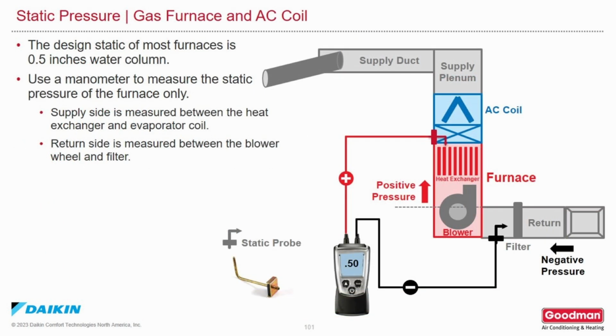When you're taking static pressure readings for a gas furnace with a coil, the design static of most furnaces is approximately 0.5 inches of water column. Use a manometer or magnehelic to measure the static pressure for the furnace only. Supply side should be measured between the heat exchanger and the evaporator coil. Return side should be measured between the blower wheel and the filter.